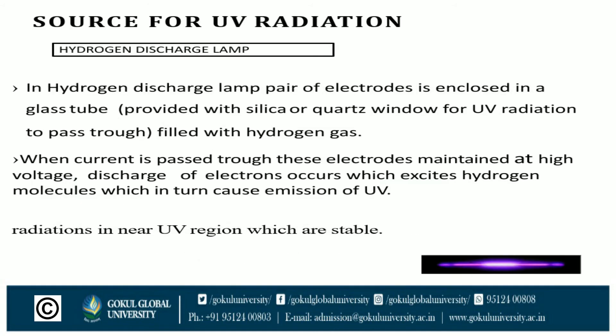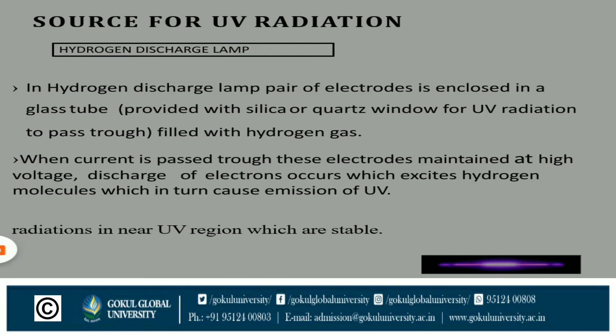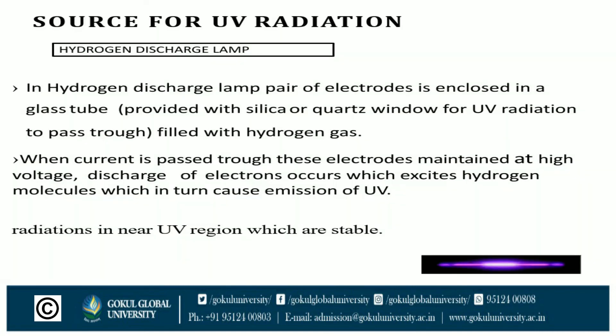The source for UV radiation: the hydrogen discharge lamp. In the hydrogen discharge lamp, a pair of electrodes is enclosed in a glass tube filled with hydrogen gas. When current is passed through these electrodes maintained at high voltage, discharge of electrons occurs which excites hydrogen molecules, which in turn cause emission of UV radiation. The hydrogen molecules are excited from the ground state to the excited state and give UV emission.